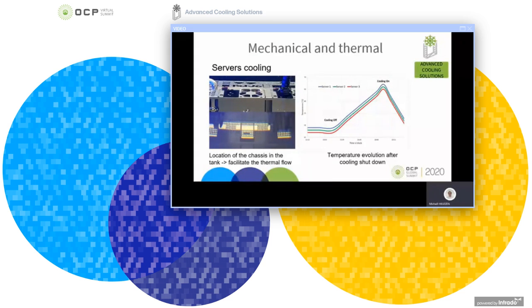Even if the tank was not full for this test, and the time for heating the liquid remained linked to the power of the submerged server, the temperature rise of the liquid is slow because it is directly linked to the thermal inertia of the liquid. It means that when this type of issue happens, it leaves time for a technician to intervene and resolve it quickly. Even if the intervention does not take place, as the rise of the temperature is gradual, it will avoid stressing the components too much before they fail.